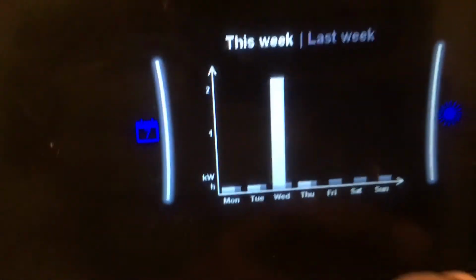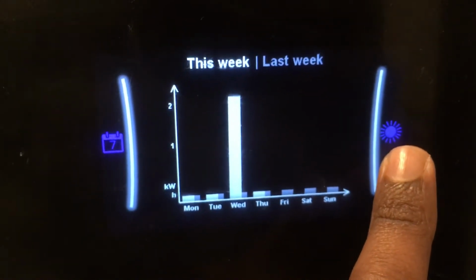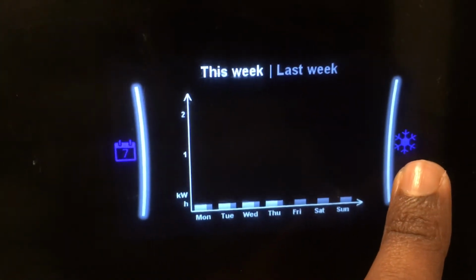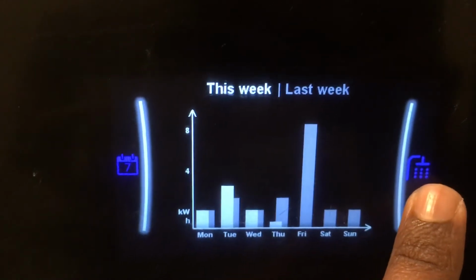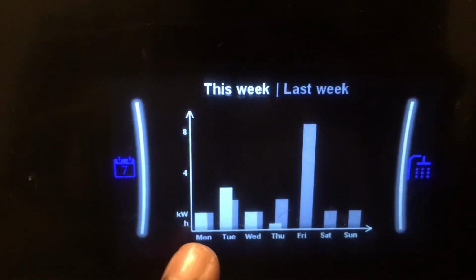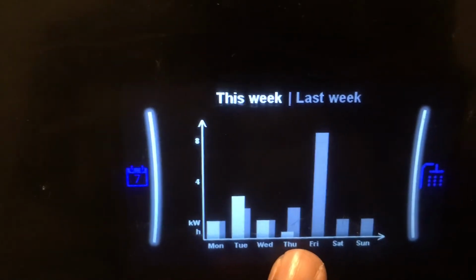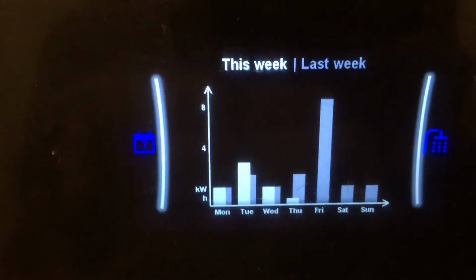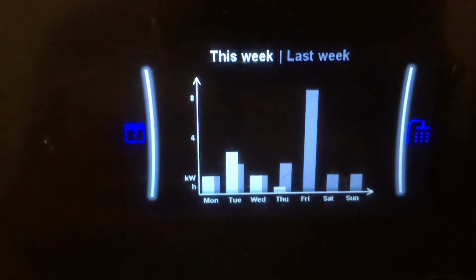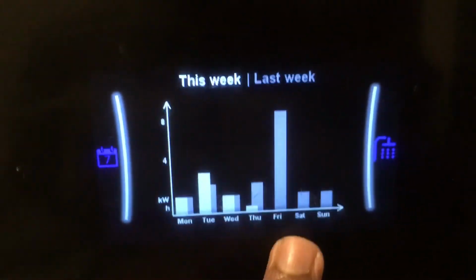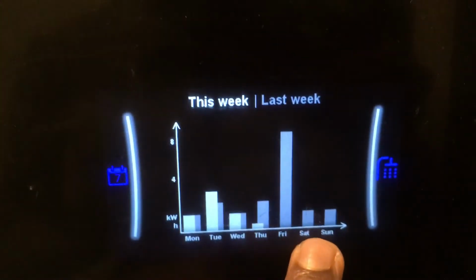This means yesterday it consumed about 2 units for heating the floor, and this is in sun mode, which is heating, and this is chill mode, which is cooling. I think this is never going to work in Ireland. And this is the tank heating mode, and for the tank heating for the past 7 days, it has consumed so much energy. Every Friday it usually consumes a lot of energy because there is a water cleaning cycle, something like that, where it heats up the water to a greater extent, like 60 degrees, and it consumes so much energy. This will happen tomorrow as well.